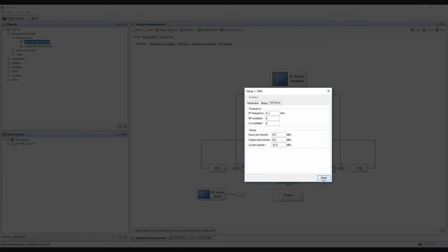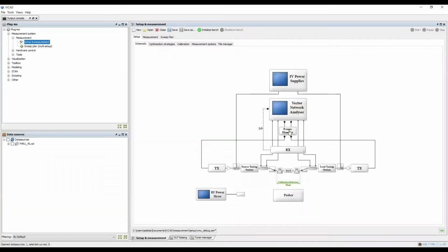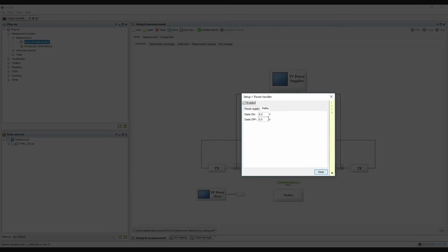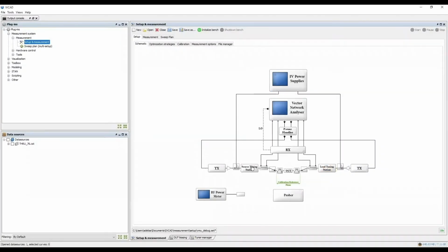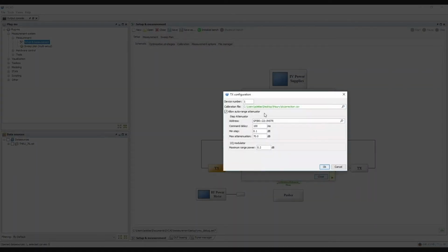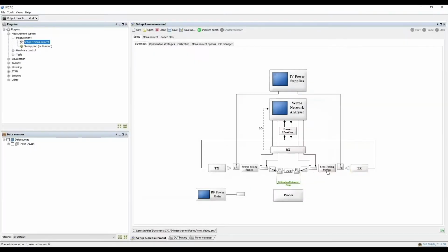We then need to set up the signal control unit, or power handler, where we set the maximum I and Q voltages for the on and off states of the modulators. After that, we need to configure the transmitter modules on both input and output of the DUT that are comprised of the frequency up converters and step attenuators.